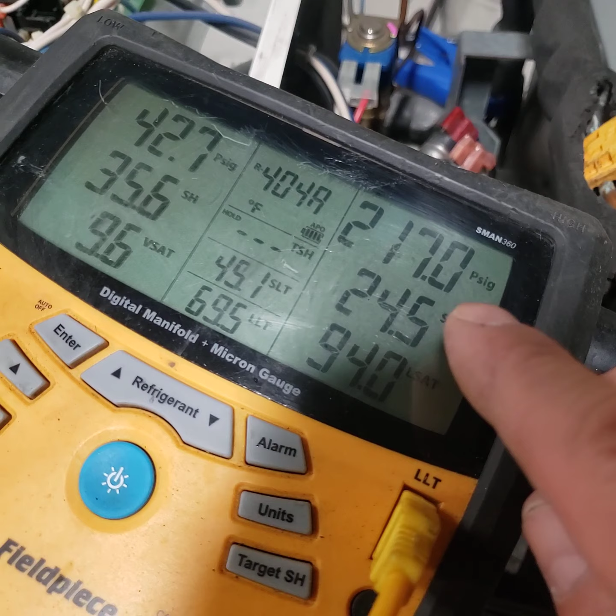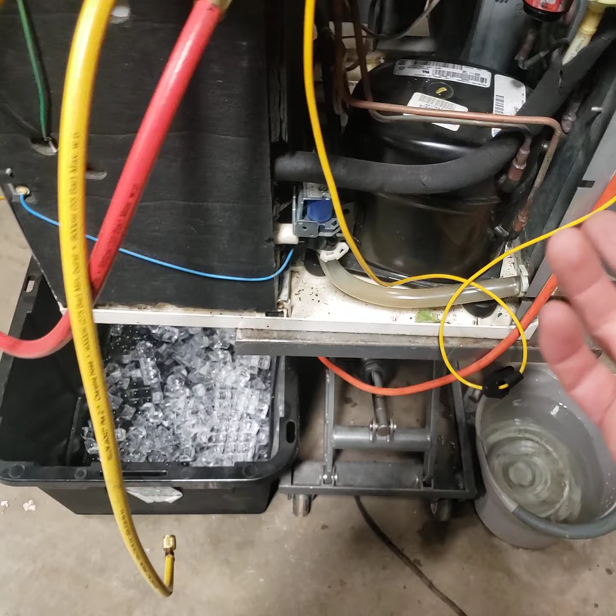Okay, so now as we see, we're going to 9 degrees, which is really low. Now remember, this was like 230 earlier, so again everything changed after a while. So again, I'm gonna tell you one more time for a quick check, because I'm doing this for a long time. I can know by touching. If you touch this pipe here and you can't hold it for more than 5 seconds or 3 seconds, it's gonna hurt you. The compressor is running.